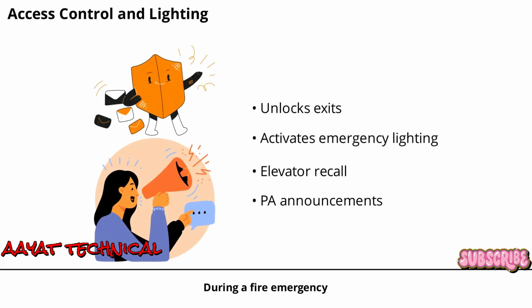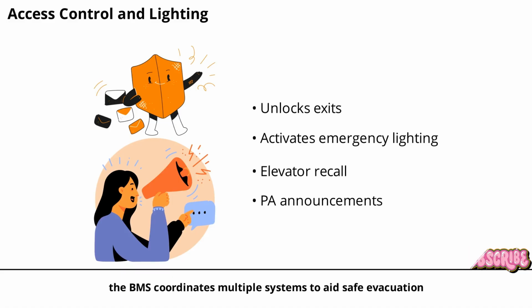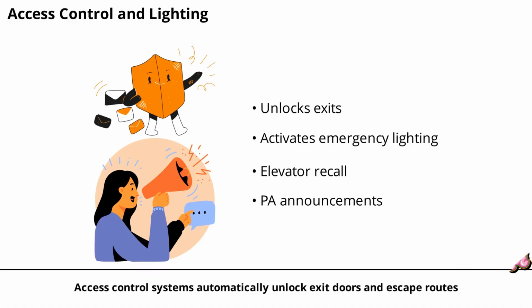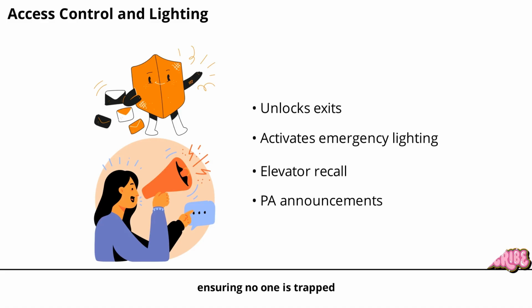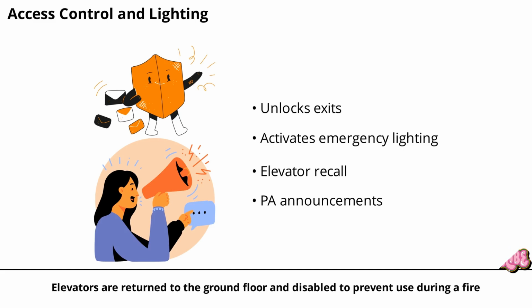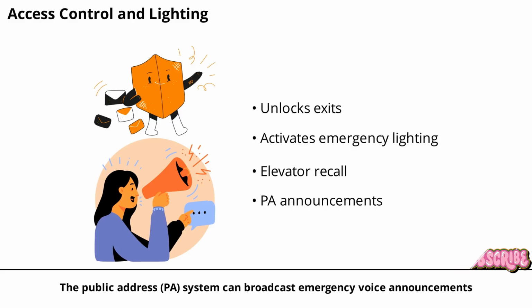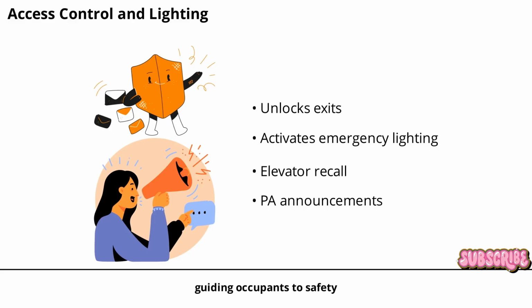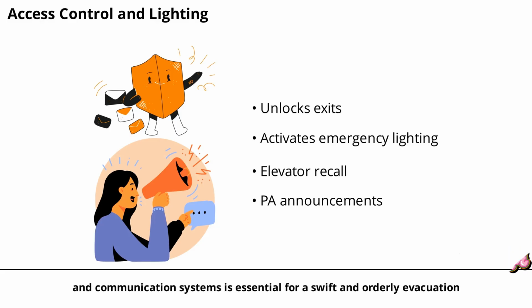During a fire emergency, the BMS coordinates multiple systems to aid safe evacuation. Access control systems automatically unlock exit doors and escape routes, ensuring no one is trapped. Emergency lighting switches on to illuminate escape paths, even in smoky or dark conditions. Elevators are returned to the ground floor and disabled to prevent use during a fire. The public address (PA) system can broadcast emergency voice announcements, guiding occupants to safety. This seamless integration of access, lighting, and communication systems is essential for a swift and orderly evacuation.